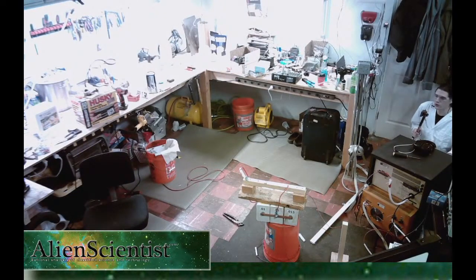So you guys can hear, I'll just tell you what voltage we're at and what we're about to do. We're going to give these caps a full voltage test. We're going to take them up to their 45 kV rated maximum, and we're going to hope that their polypropylene dielectric and oil-filled systems do not blow through and possibly blow up.